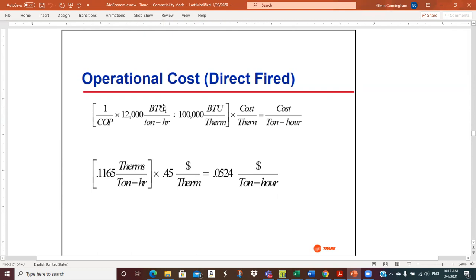Okay. So this is going to get me therms per ton hour of refrigeration, and then I multiply it by the cost, dollars per therm, and I get dollars per ton hour. For the direct fire, the COP was 1.03. It says that in the notes below. So you take 12,000, divide by 1.03, and then divide by 100,000, and I guess you get 0.1165 therms per ton hour, and then times the rate of 45 cents per therm, and there we go. So that's 5.24 cents per ton hour for the direct fired to provide the refrigeration.